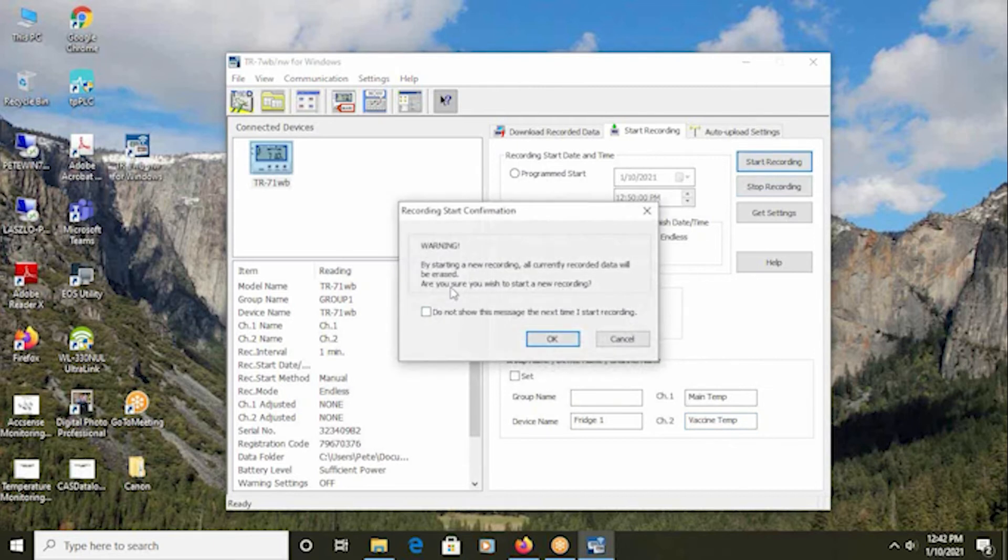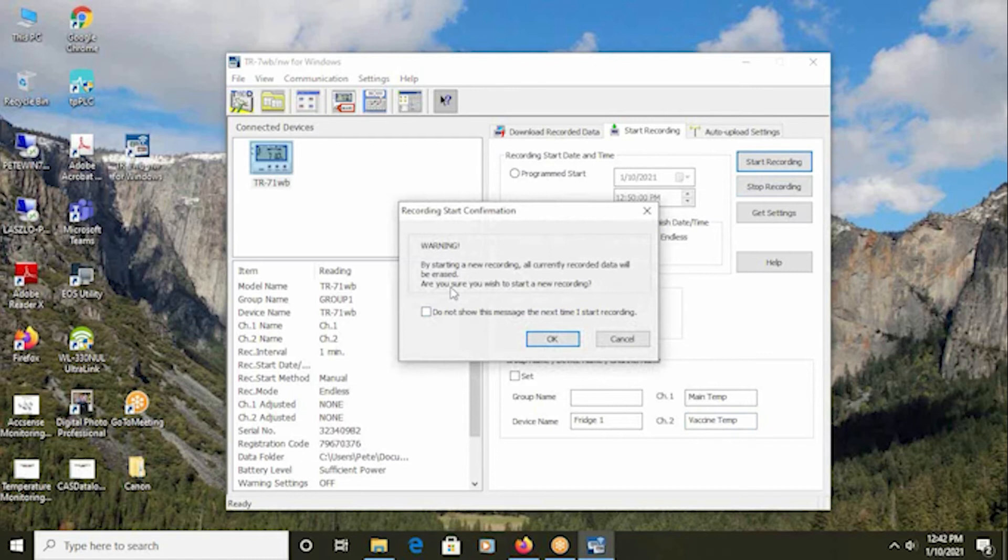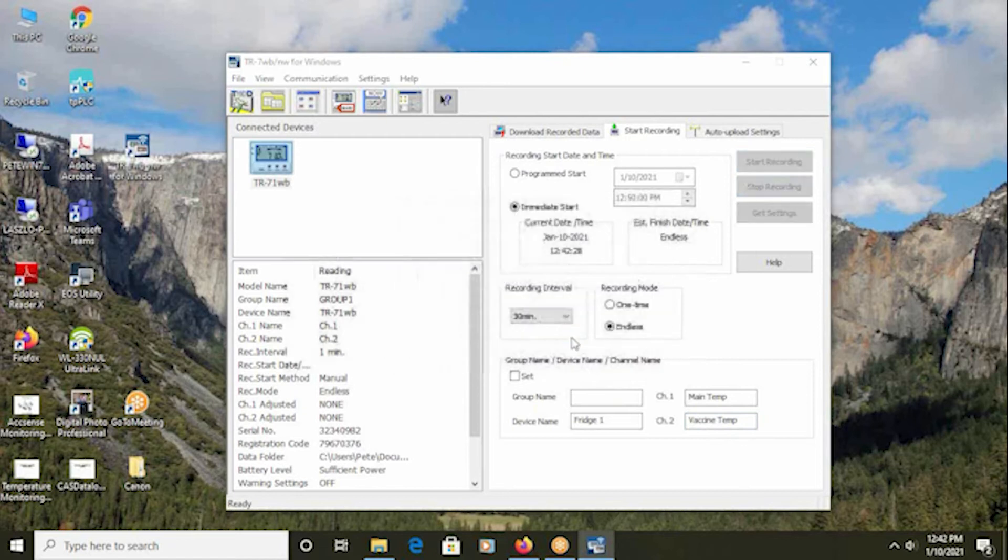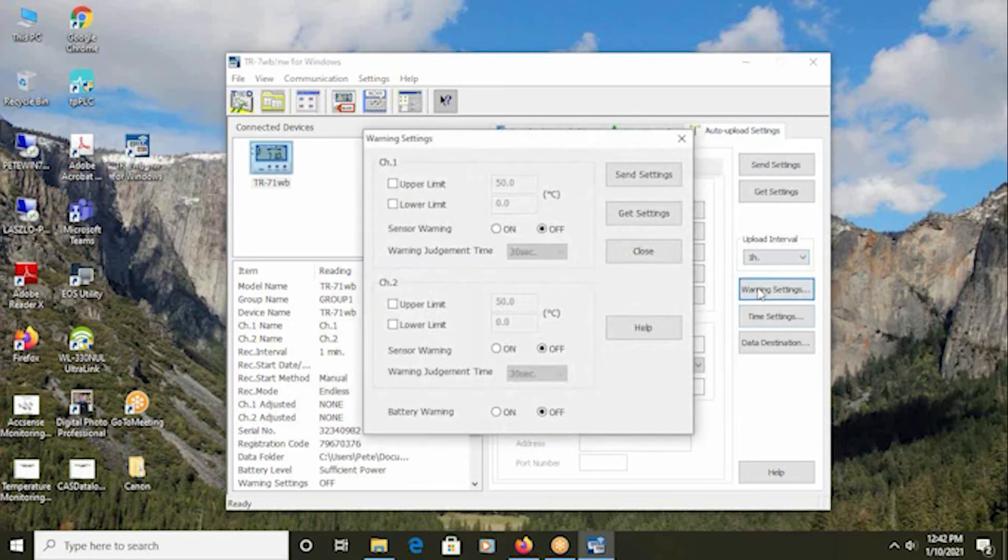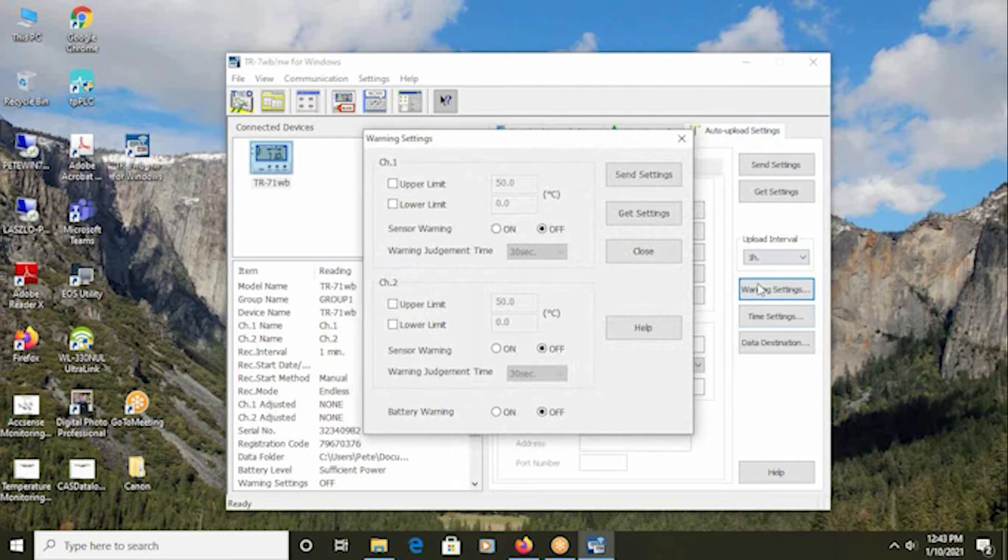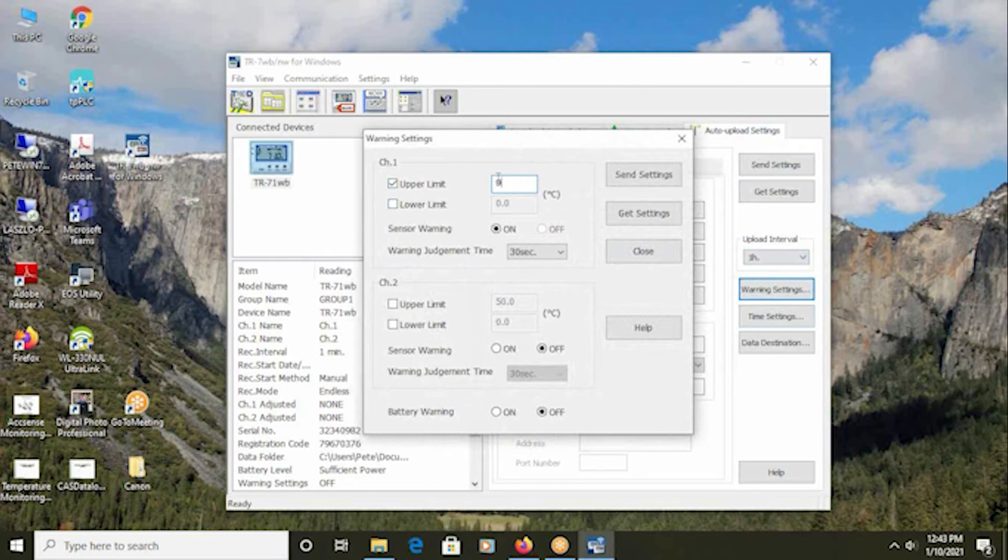This does give you the prompt that if you are starting the recording, if you already have data stored on the logger, that will be deleted in order to start a new recording session. So it's important that if you have previously recorded data that is important to you, that you download that data directly from the logger before proceeding with starting a new recording. Next, click on the auto upload settings. The first thing to do is to configure the warning settings. This is where the upper and or lower limits on a per sensor basis can be configured to trigger the alarms that will be sent to you. So for instance, if I'm in a 5 degrees C freezer and I want to be alerted if the temperature rises above 9 degrees C, put 9 in. If I don't have a lower limit, leave the box unchecked.